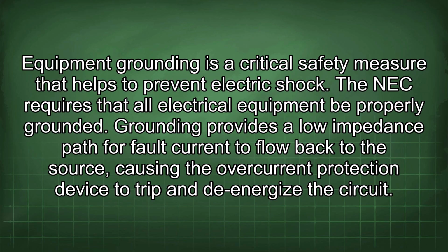Equipment grounding is a critical safety measure that helps to prevent electric shock. The NEC requires that all electrical equipment be properly grounded. Grounding provides a low impedance path for fault current to flow back to the source, causing the overcurrent protection device to trip and de-energize the circuit.